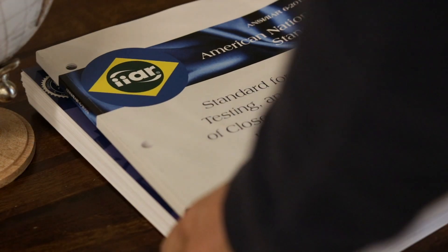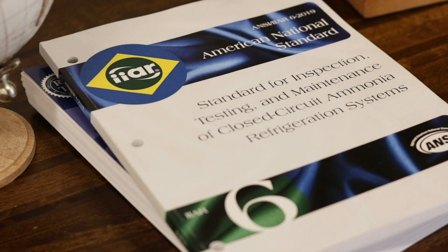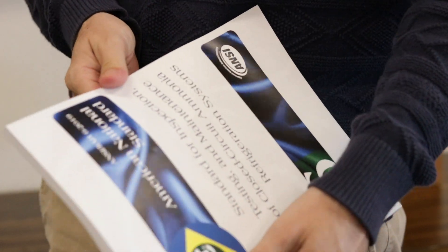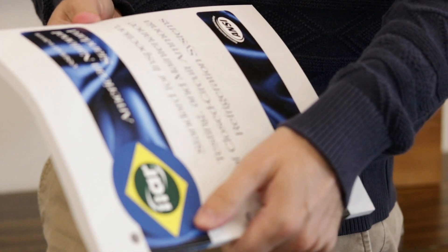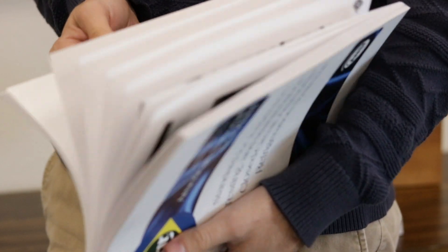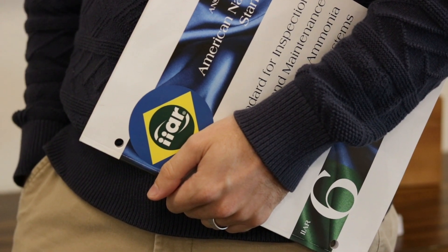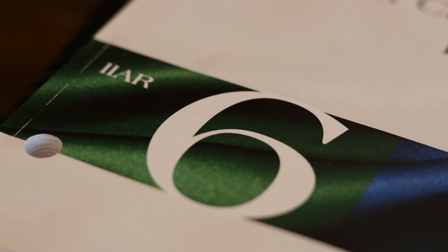The checklists contained in IIAR 6 Appendix B are derived from a legacy document named IIAR Bulletin 109. For years, the Bulletin 109 Checklists, or B109s, served as the gold standard for documenting annual mechanical integrity inspections for ammonia refrigeration equipment. In 2019, IIAR retired Bulletin 109 when the first edition of Standard 6 was published. Standard 6 addresses the minimum requirements for inspection, testing, and maintenance of ammonia refrigeration systems, and includes slightly altered versions of the B109s in Appendix B.